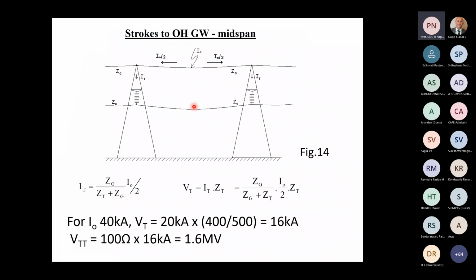Now, knowing all these unacceptably high values, suppose we provide an overhead ground conductor. So now what happens is, suppose I consider a 40 kiloampere stroke to the ground conductor. It divides into two portions of 20 kiloamperes each on the two sides of the ground conductor. That 20 kiloamperes comes here and divides between the forward path of the ground conductor and the tower surge impedance here. That's a very big advantage for us. So now you will find that the current to the tower is given by the surge impedance of the line divided by the sum of the surge impedances of the two objects. So that comes to 16 kiloamperes. So it gets reduced from 20 kiloamperes to 16 kiloamperes. So for 16 kiloamperes, for 100 ohm surge impedance, it gets reduced to 1.6 megavolts.